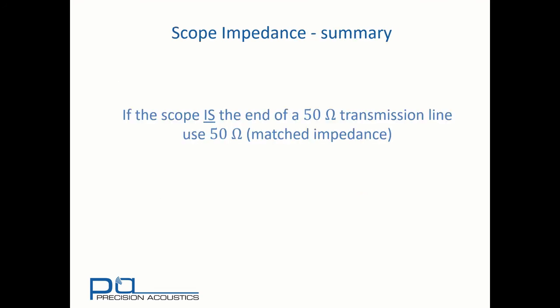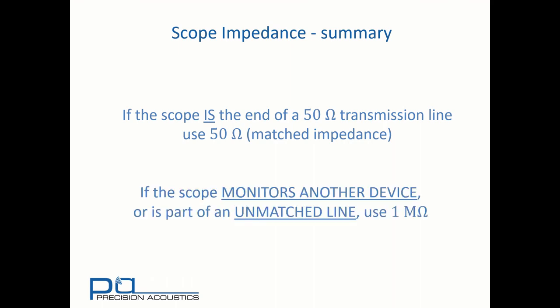To summarize: if the scope is at the end of a 50 ohm transmission line, then you must use 50 ohm impedance to ensure that you have a matched impedance. If the oscilloscope monitors another device, or is part of an unmatched line using an unbuffered hydrophone, you must use one megaohm impedance. We hope you found this interesting — come back and find some more of the Precision Acoustics tutorial videos. We'll see you next time.